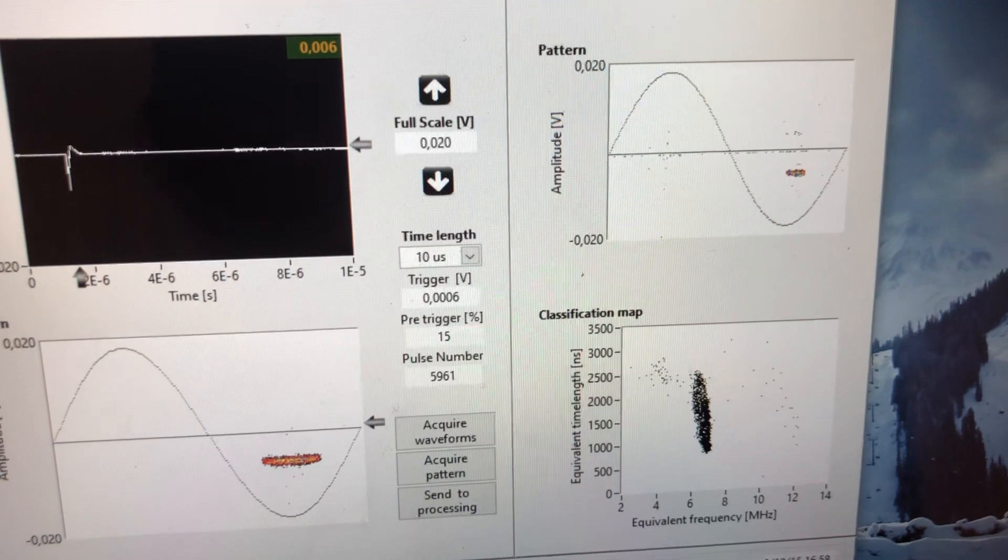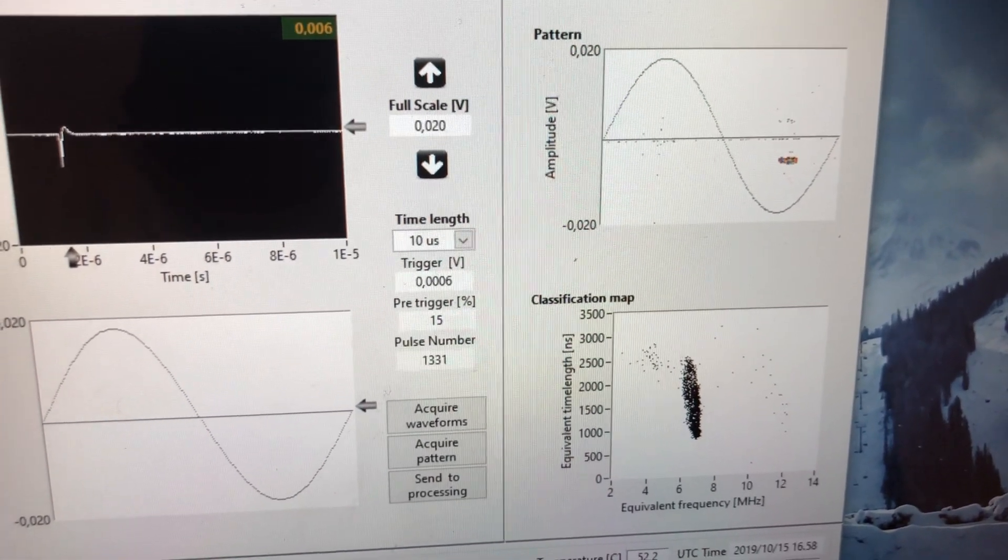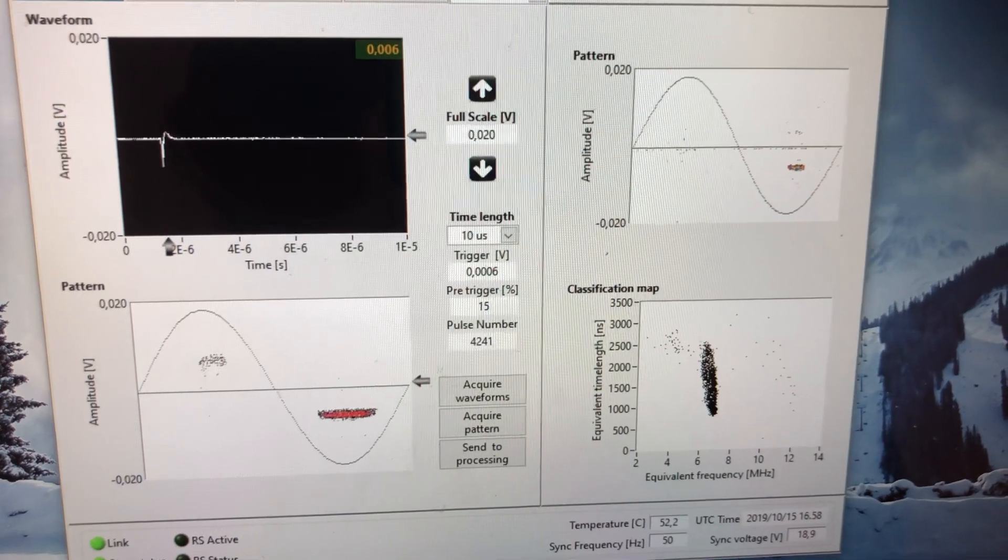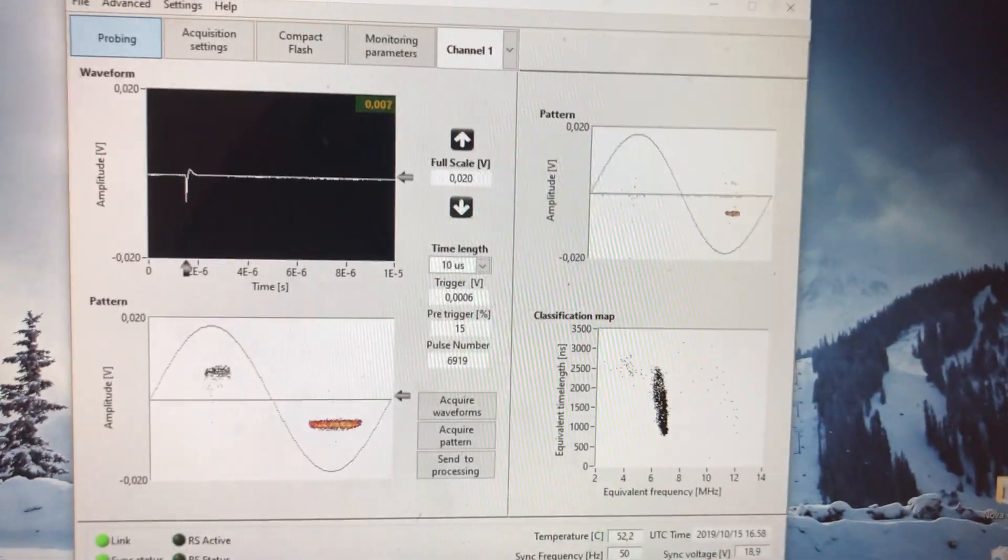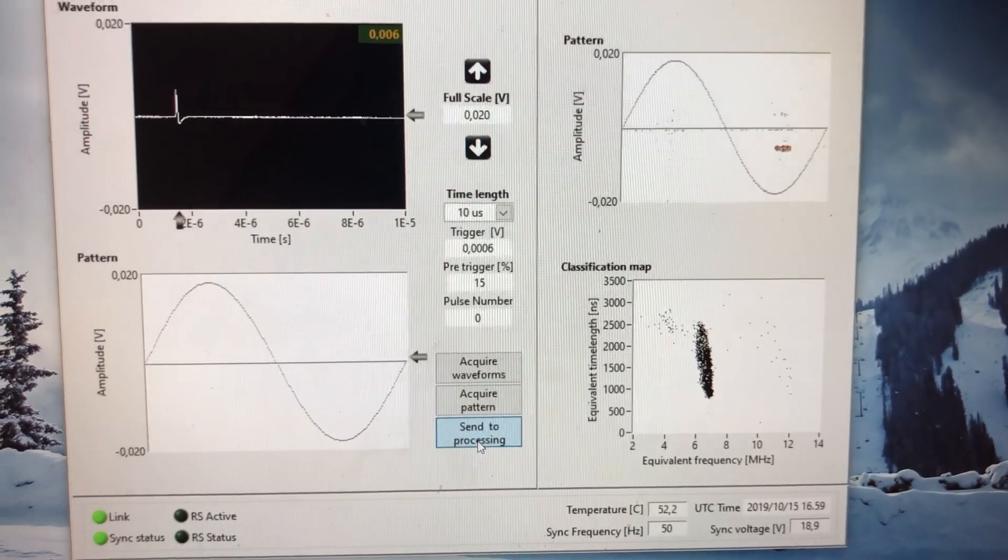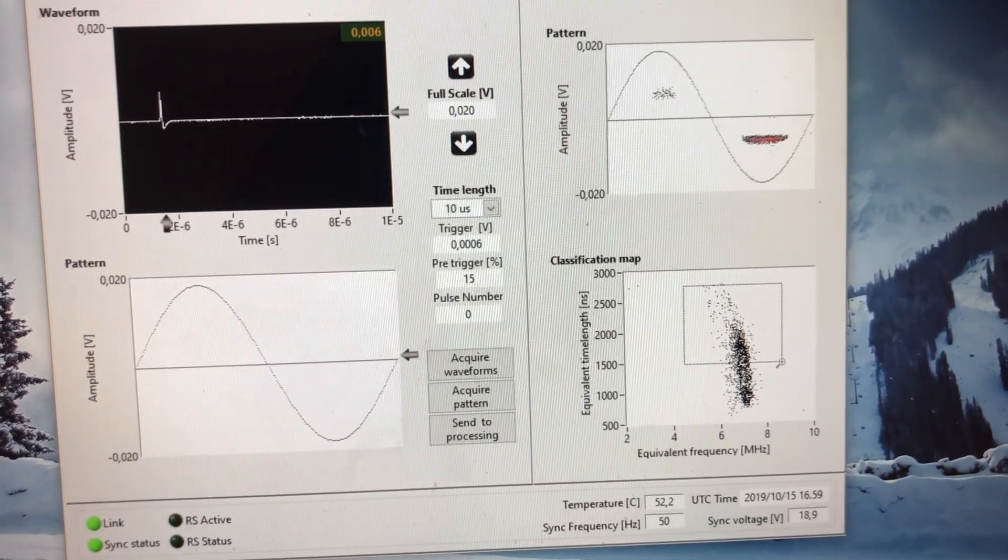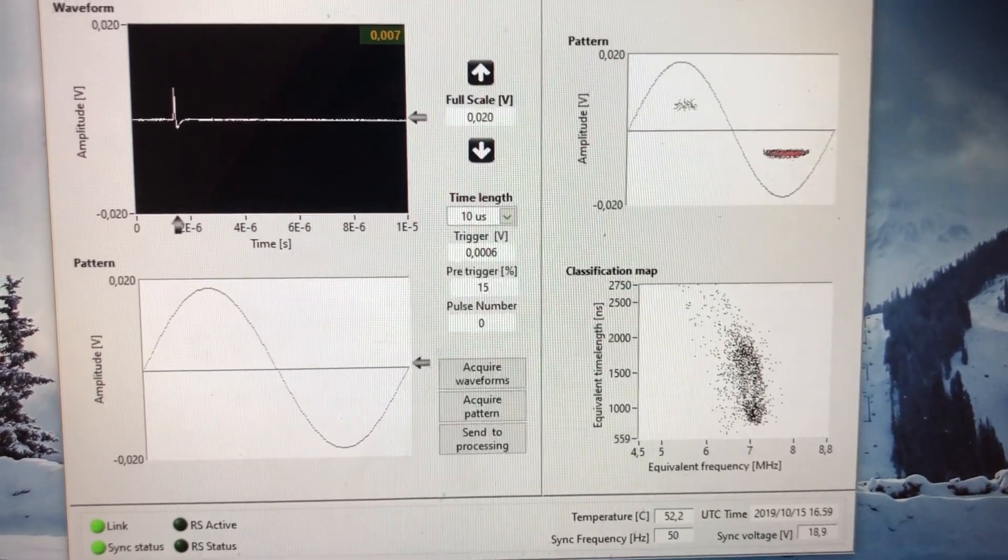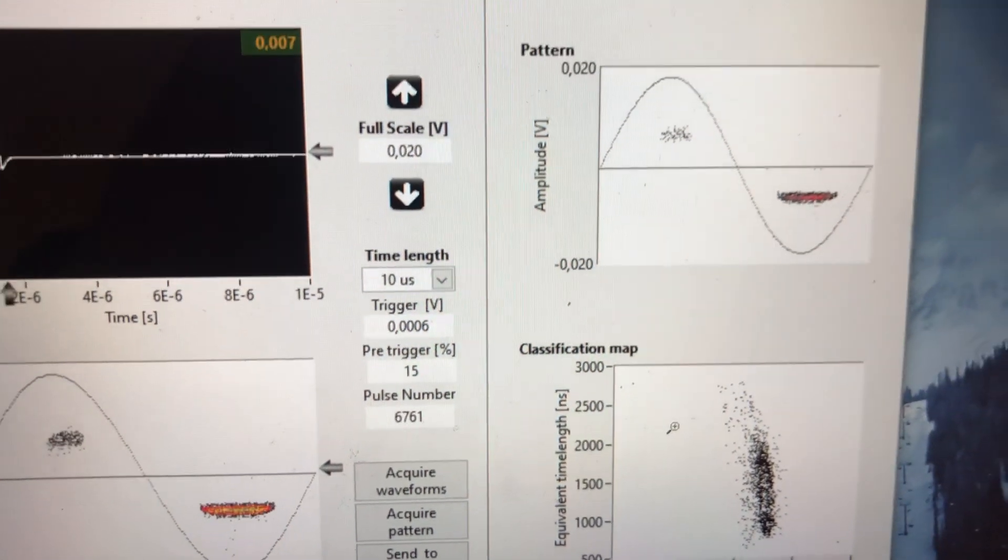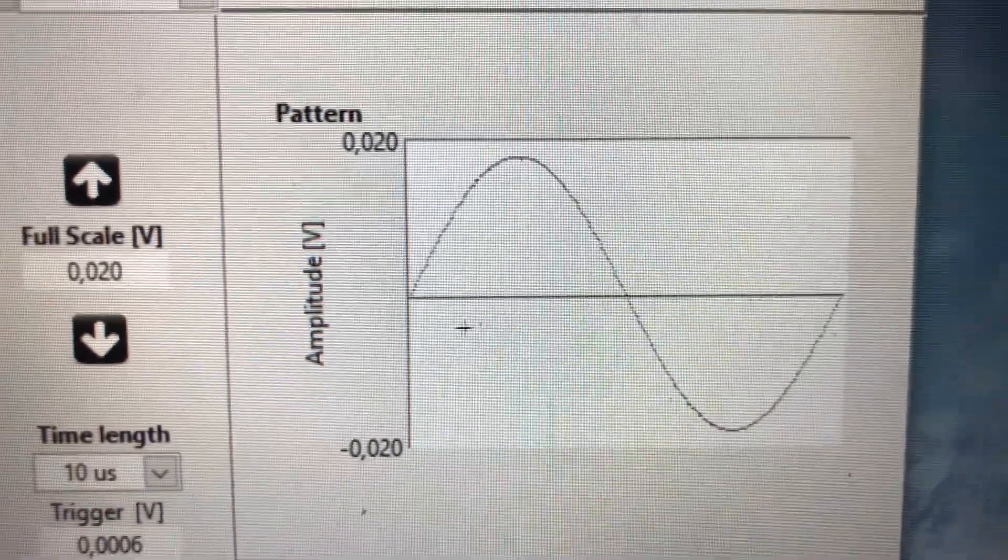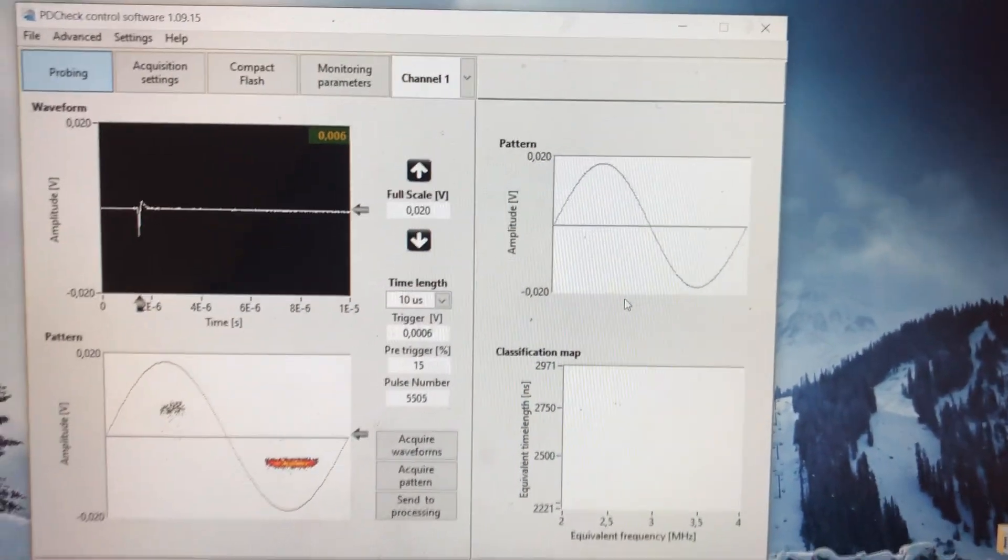The first thing you see is that the negative Corona is spreading, which means that it starts now even before phase shift wise spreading. And at one point in time, I should start getting the positive side Corona. Let's see. And as we can see, now I got it. Since it has a pretty high repetition rate, the counter goes quite quickly to 10,000. Still, I'll try and send it to processing before the counter reaches 10,000. Let's say right now. And here right now, what I see is more or less just the Corona because the noise, there's too little noise, not enough time to pick it up. There is a little bit of noise, as you can see here. So if I'm just to choose that, I will not see Corona, but just the points which happen due to certain noises.